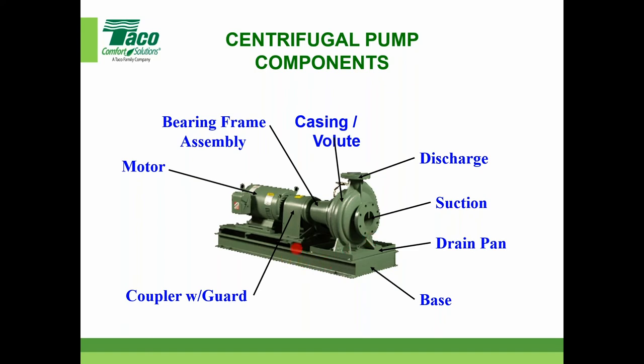But nonetheless, aligning these, there's two shafts. This is considered a split coupled pump. That means there's a shaft attached to the impeller, and then there's the motor shaft, but they're not one and the same. A direct coupled pump, a close coupled pump, those are two terms that mean pretty much the same thing: the motor shaft would be the impeller shaft. So in any split coupled pump, especially base mounted split coupled pumps, alignment is one of the key elements to proper startup and operation of these base mounted pumps. And that alignment is not just vertical and horizontal, it's angular as well. Really it should be laser aligned.